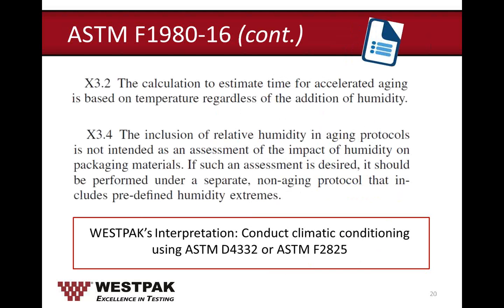The first change is in section X3.2: the calculation to estimate time for accelerated aging is based on temperature only, regardless of any addition of humidity. We tell our customers, please do not consider relative humidity when calculating accelerated aging time. This new statement makes that very clear.